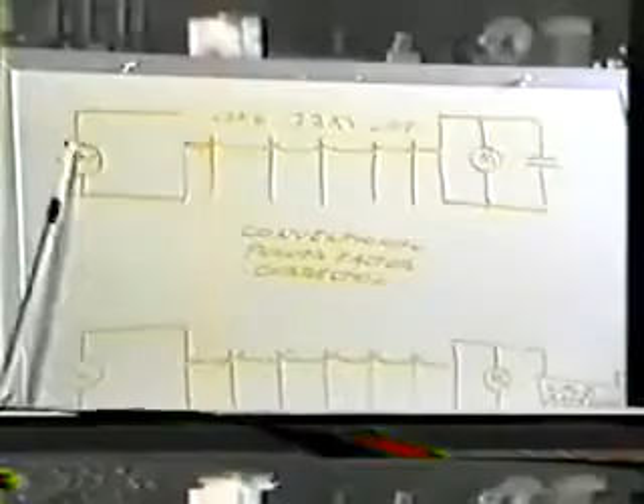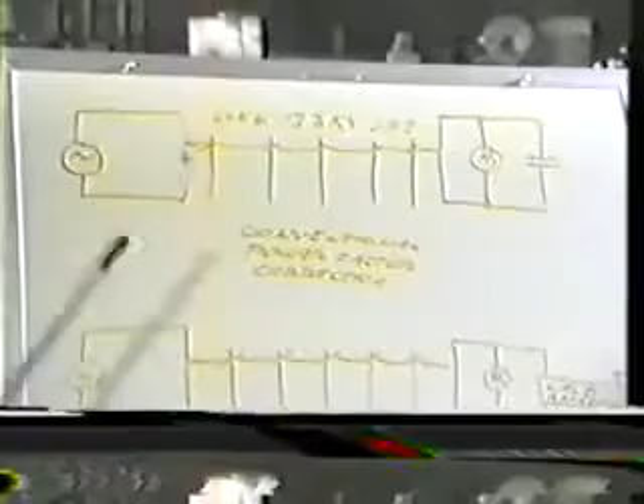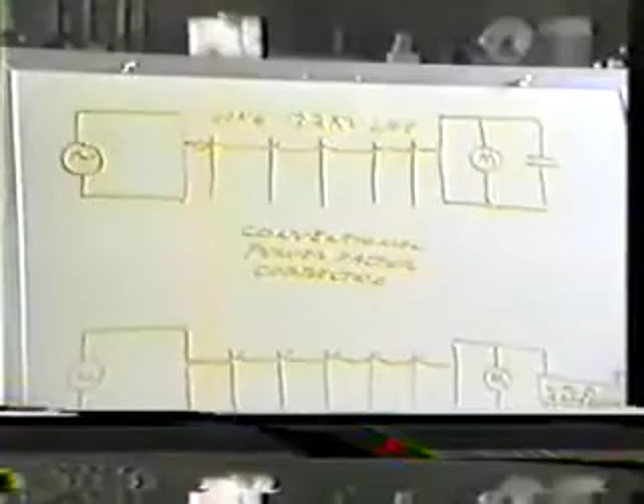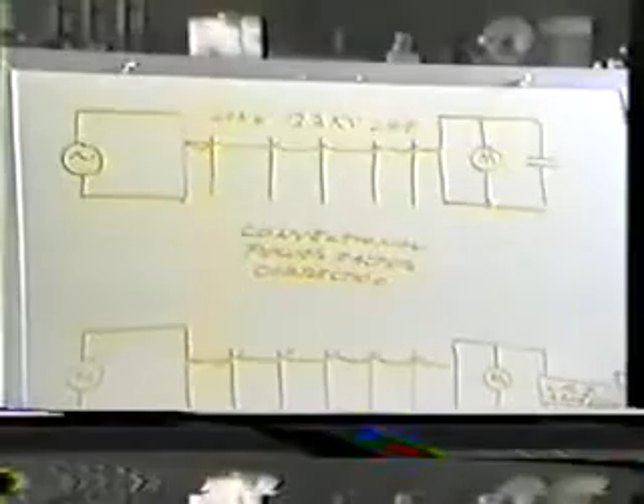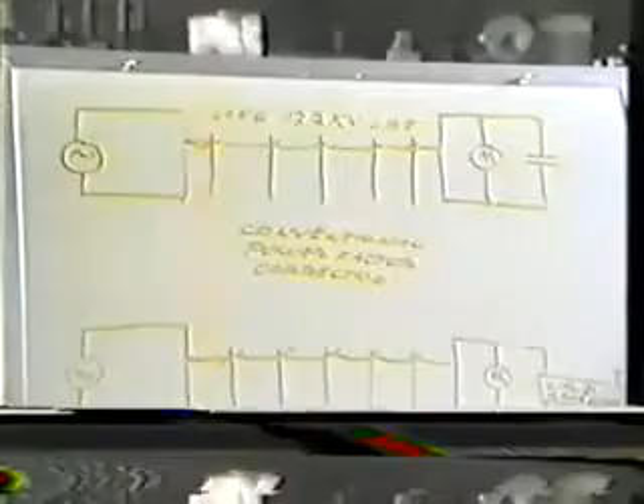Normally what's done is a capacitor is hooked across the motor to provide the magnetizing energy, because capacitors will generate magnetizing energy, and that relieves the transmission line of the duty. Further, the magnetic induction, which is the prominent element in most transmission lines, being that the voltage doesn't operate much above your low voltage points, usually less than 66 kV, which most feeder lines are, you don't have enough dielectric induction for them to be anything more than an inductance coil. So it's just like a big transformer winding.